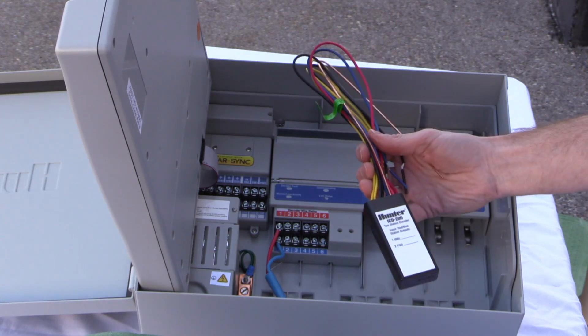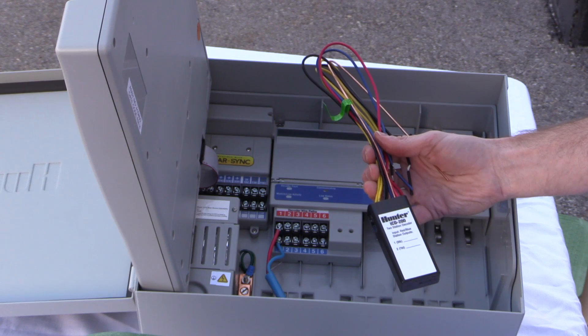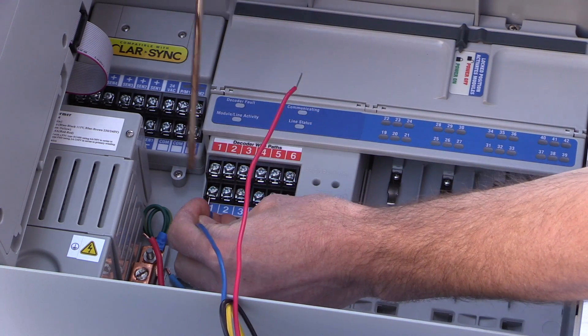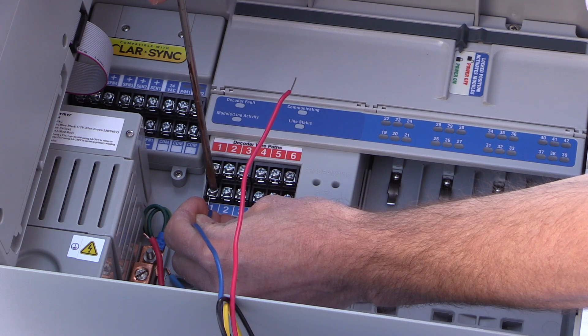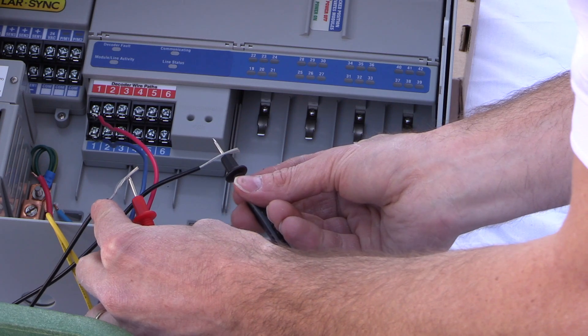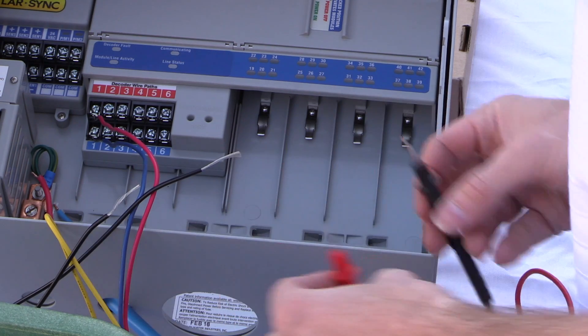You can also take a spare decoder and connect it directly at the controller to verify that the controller is operating properly. A common rookie mistake is to assume that the controller itself is the source of field issues. In a vast majority of reported problems, the issue will be in the field wiring.